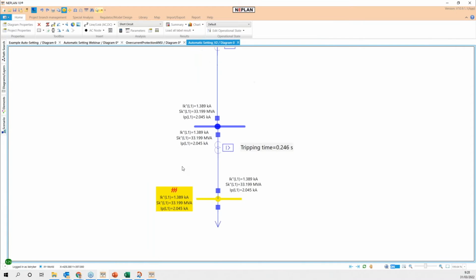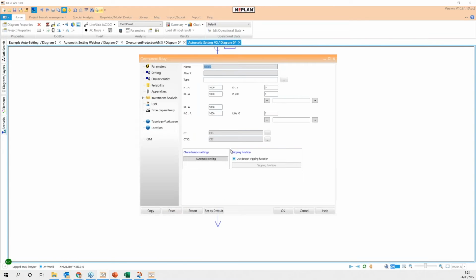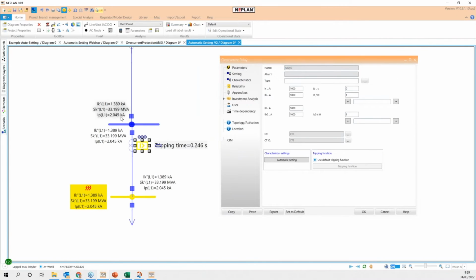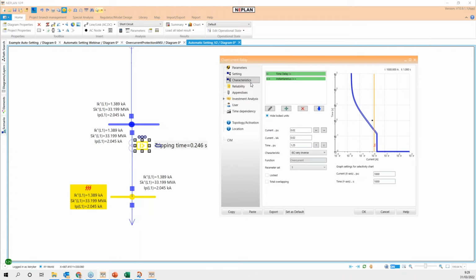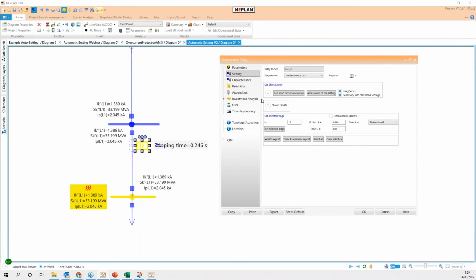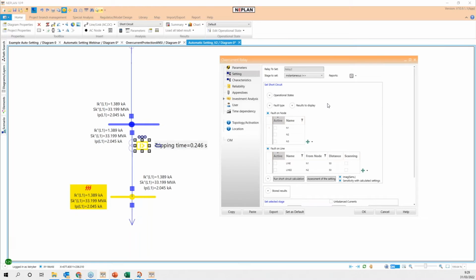How can we improve that? Let's open here the NEPLAN characteristic of the overcurrent relay. In this case, let's see, for example, what is the current setting that we have. NEPLAN allows us to see directly in the window of the relay that for that short circuit level, the operation is out of the scope of the instantaneous unit. Can we change that manually? Yes, we can modify the setting of the protection according to the possibilities of the system. But let's allow NEPLAN to determine the best tripping, the best backup, the best pickup setting of the protection.